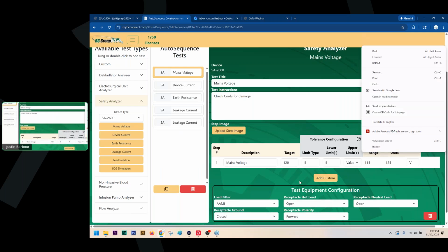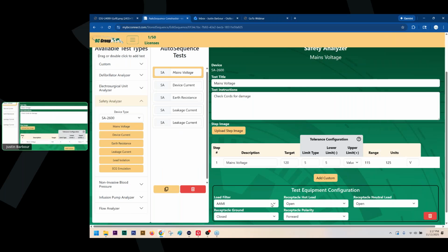Down here is where we set up our test equipment. You select what type of load you want—AAMI, IEC—and then select what you want with all the buttons on the front of your electrical safety meter. You can see forward polarity, and I'm closing all the relays—this comes into play later, like how we open ground and then close ground for leakage testing. This is where you'd build that out.